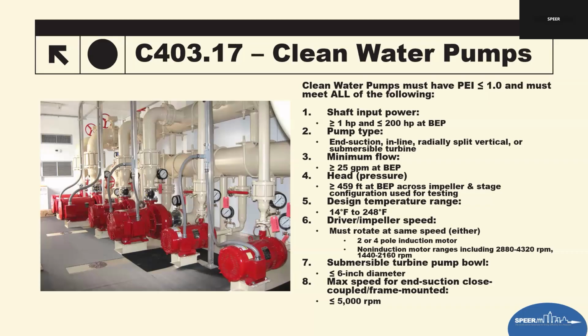So, plan review tips here. Confirm the pump type is within those allowed categories. Verify the PEI is less than or equal to 1 from the DOE manufacturer certification. Check pump performance so the gallons per minute, the head, and the temperature range match code criteria. Confirm the motor type and rotational speed fall within the allowed ranges. And then identify whether the pump falls under any exemption. If so, it needs to be clarified accurately in the documentation.